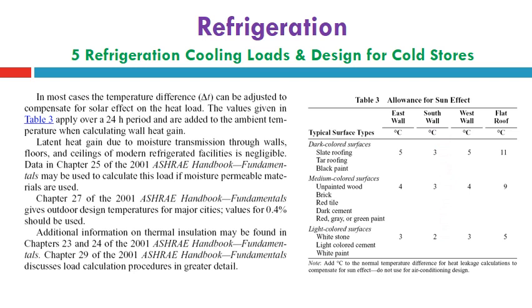Especially, this table is taken for the upper part of the earth, above the equator, where the sun rays cannot reach the northern wall. However, if we design a refrigerated space in the lower part of the earth, below the equator, we will take these amounts but swap the roles: the northern wall will receive sun rays, but the south wall will have no sun rays reaching it, according to the sun's movement around the earth.